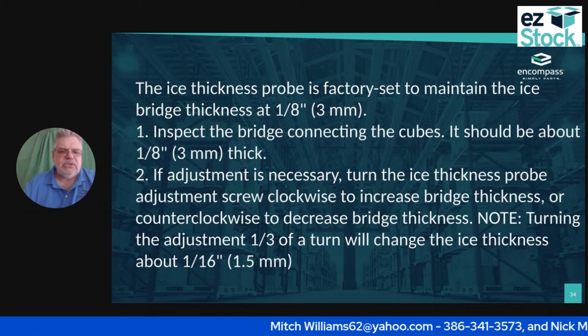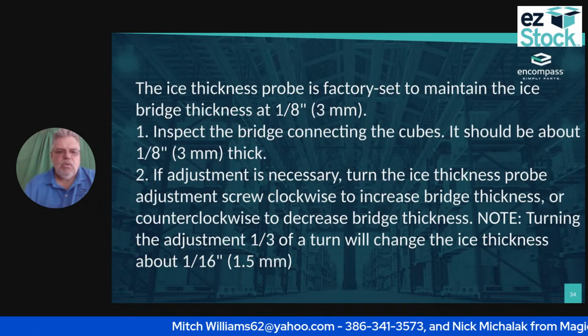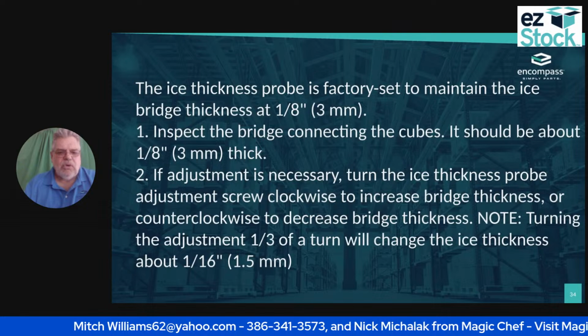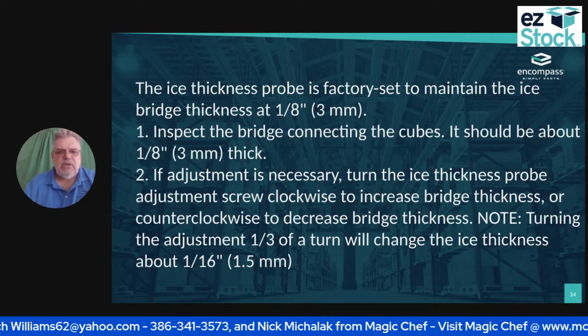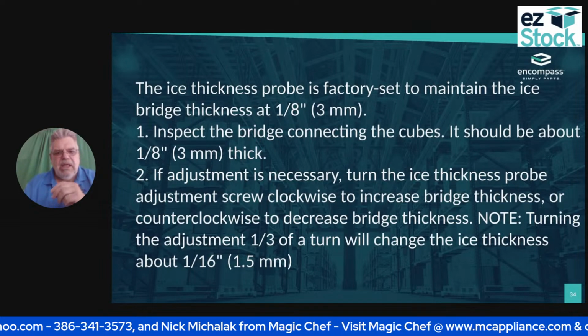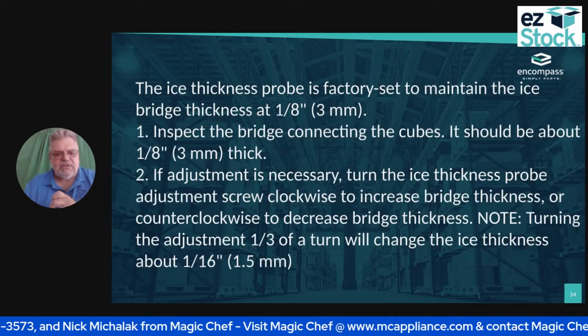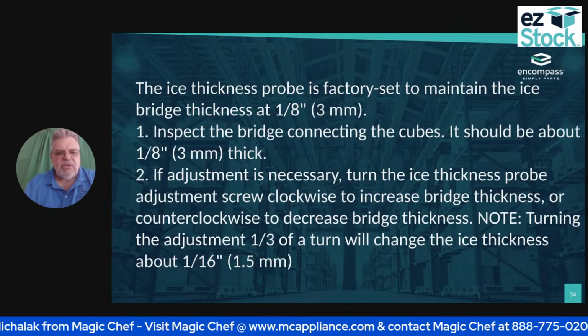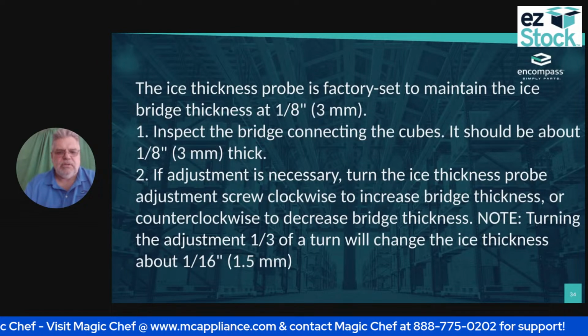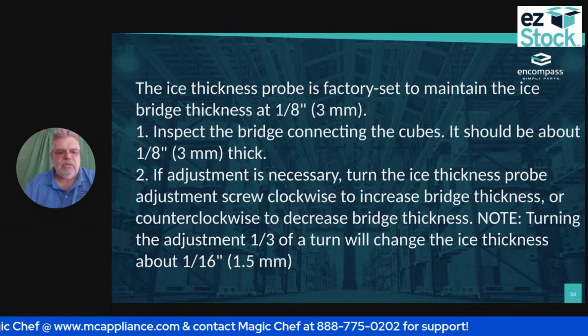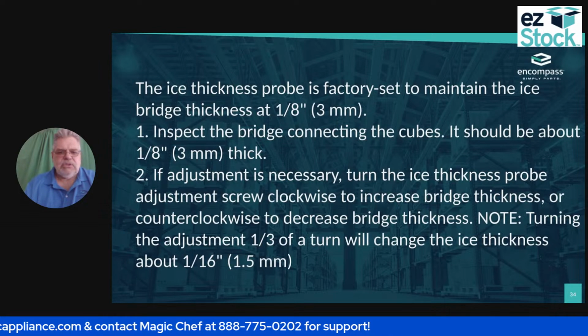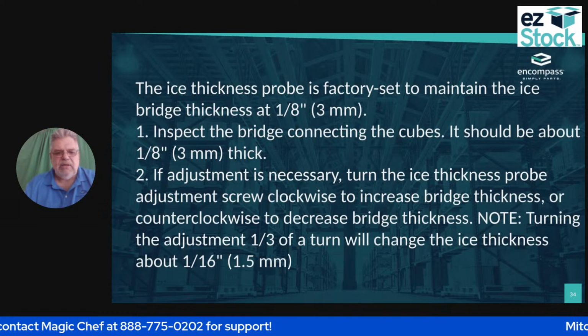So turning the adjustment a third of a turn will change the ice thickness about 1/16 of an inch. So you need to remember, if I'm turning it a third of a turn, I'm getting about 1/16 of an inch, either addition or removal of the thickness. So I should never need to turn it more than a third of a turn.